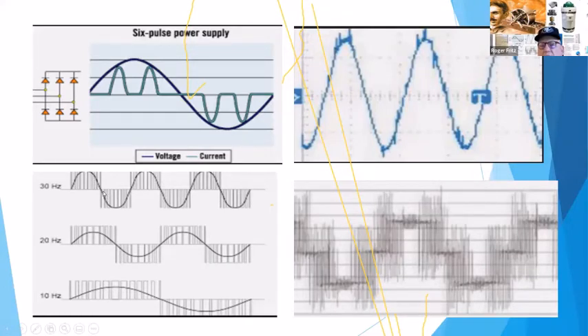You heard that a lot in the motor. You'd hear a lot of audible noise. Then they went up to roughly 1200 hertz, 1500 hertz on the transistor firing. Again, you could hear the audible noise coming from the motor. Now they're as high as 15,000 to 20,000 pulses per waveform. So it becomes a lot quieter. You can get better regulation on the motor, some of those things.